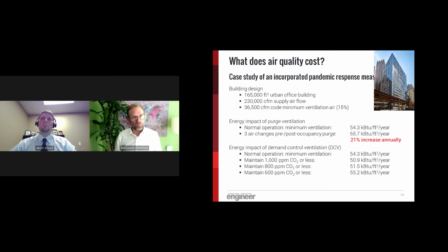The second one we looked at was the demand control ventilation, or reducing the ventilation when there are fewer people in the space. We looked at minimum ventilation, which is code, and then we looked at 3 different levels of ppm, or parts per million of CO2 in the space. At 1,000 parts per million, which ASHRAE would deem acceptable, it's calculated, we saw an energy reduction using the demand control ventilation. We looked at LEED, which has a requirement around 800 parts per million, and we saw that it increased slightly, but it's still below that code level. So it's a very effective energy measure.